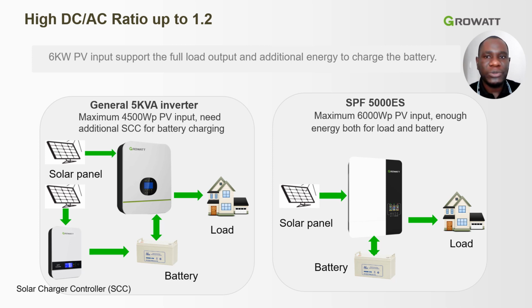If you check with other inverters on the market, you realize that they've got a DC to AC ratio which is below 1.2. The diagram shown on this presentation, the left side of it, is showing the first generation. For the first generation, you will need a solar charge controller to be able to supply your load and at the same time charge the batteries, as compared to the latest version that we have, which is the SPF 5000 ES. It can take a maximum PV input power of 6000 W, that is for the 5000 ES, of course. And it has got a built-in MPPT charge controller, meaning that you can supply your load and at the same time still have allowance to charge your battery.